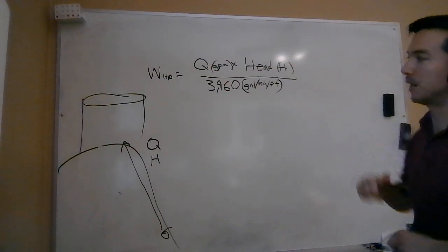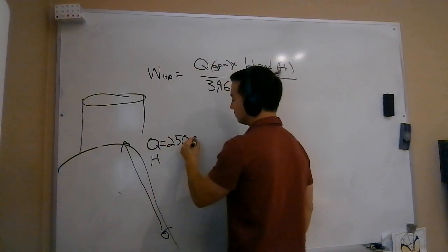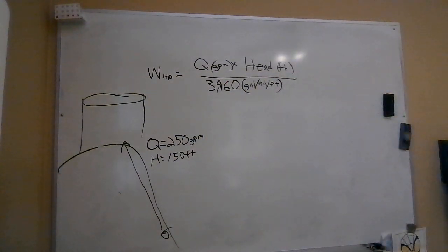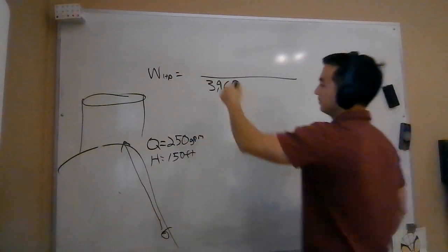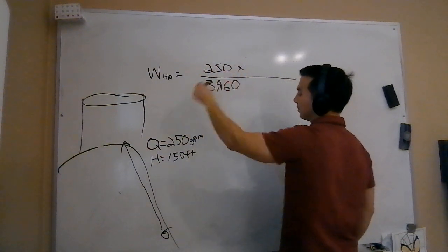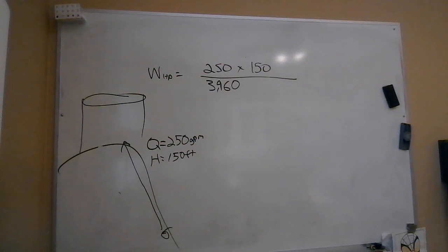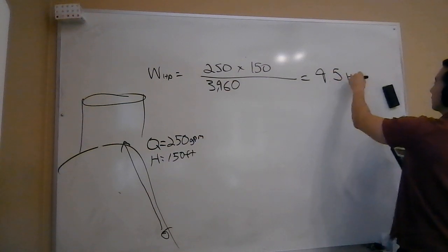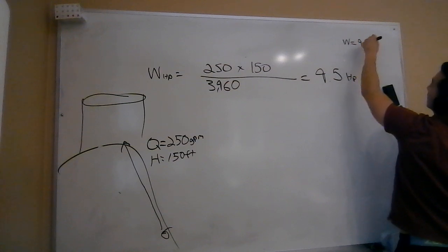For our water horsepower example, let's say our desired flow rate is 250 GPM and our total head is 150 feet. Using the formula: 250 GPM × 150 feet, divided by the conversion factor 3960, gives us a water horsepower of approximately 9.5 horsepower.